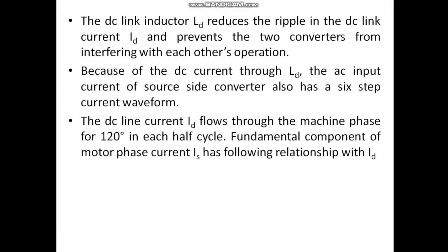So the load side converter, when working as an inverter, behaves essentially as a current source inverter, except that thyristor commutation is now performed by the motor induced voltages. Consequently the motor phase current has a 6-step waveform. See here, I said because of the DC link current and LD, my AC input current is 6-step.